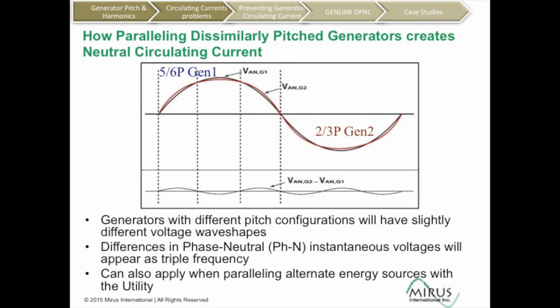So when you have these wave shapes being paralleled together on the same bus, it results in instantaneous voltages that go from 0 between the two generators up to a peak value in positive, if you're looking at the 2/3 of the red wave shape relative to the blue wave shape, and then it goes back down to 0, and then it repeats in the opposite direction. So the red is less than the blue, and we have a negative half cycle and then a positive half cycle. So now you can see that during 1/2 cycle of the fundamental voltage, we have 3 half cycles, or 3 times the fundamental frequency.